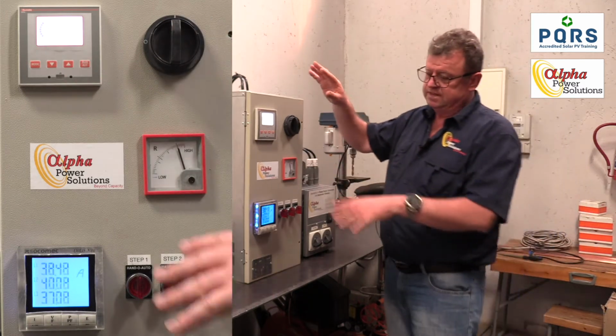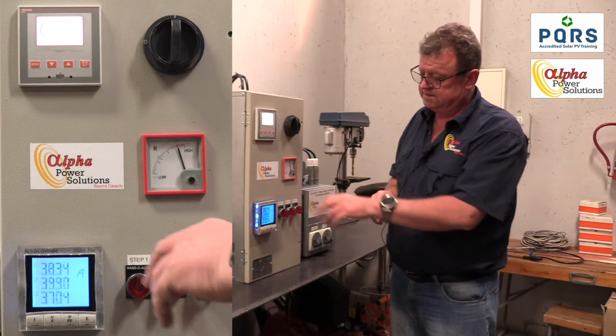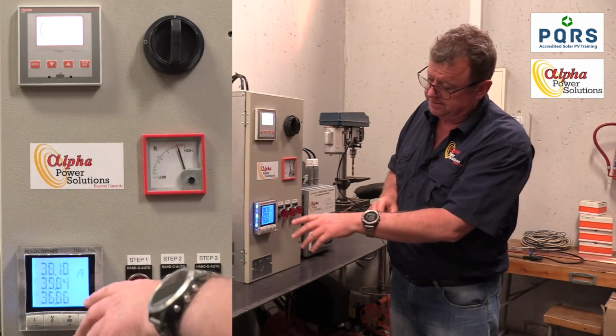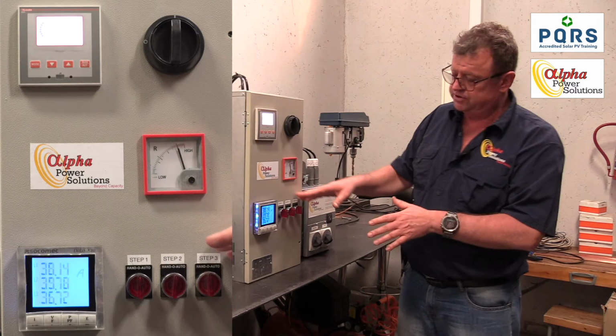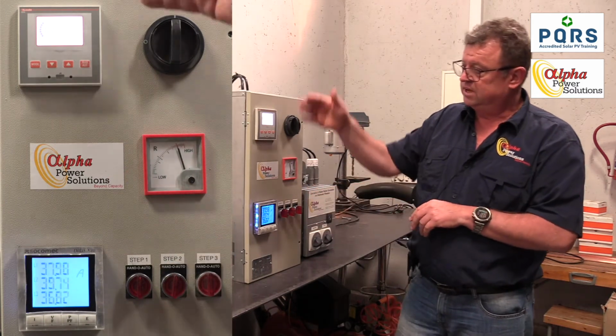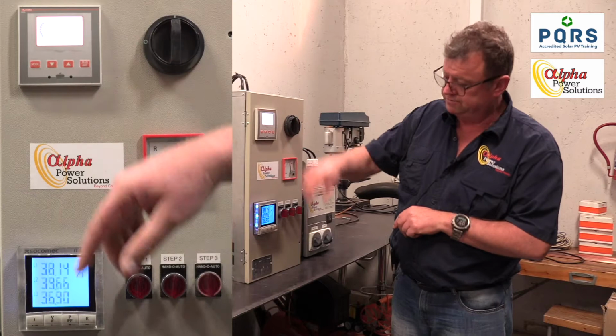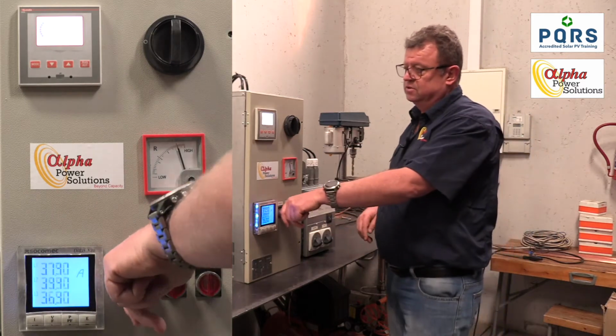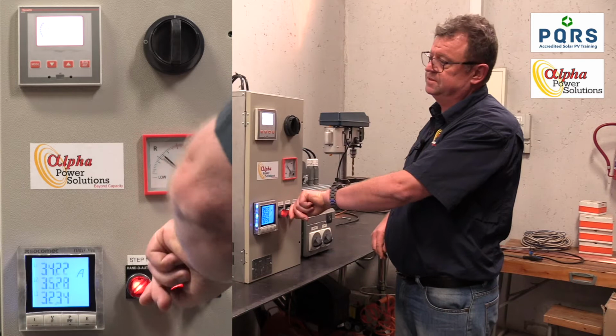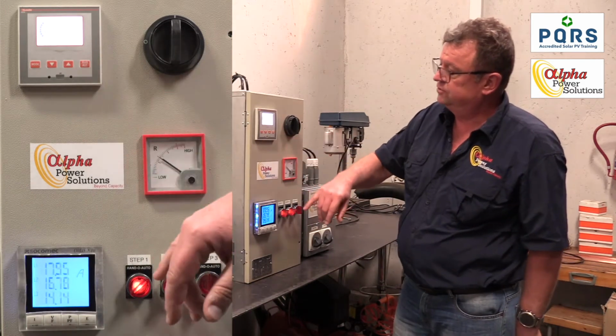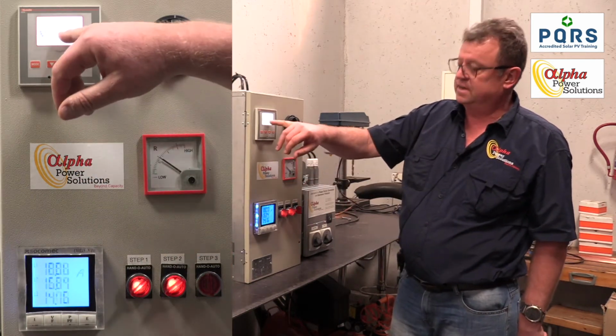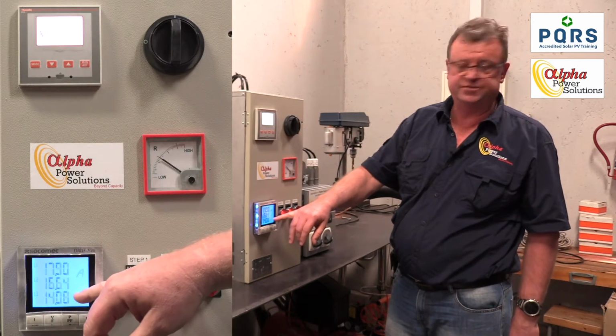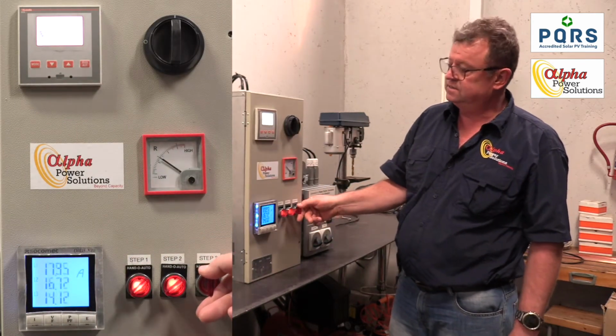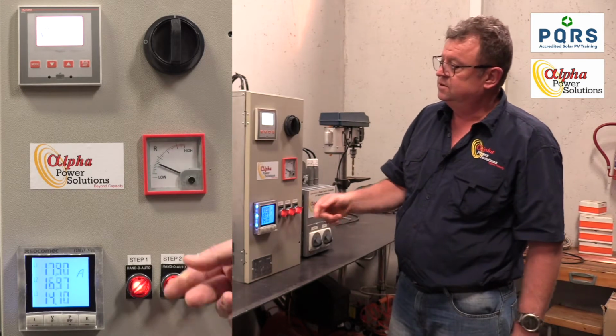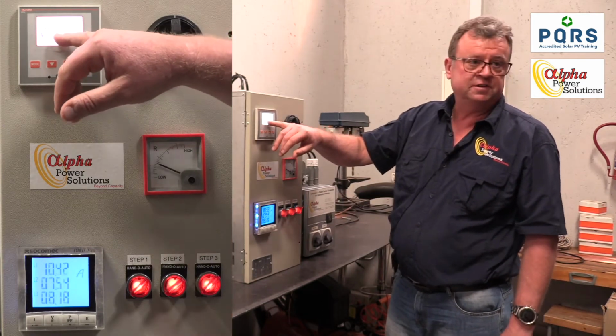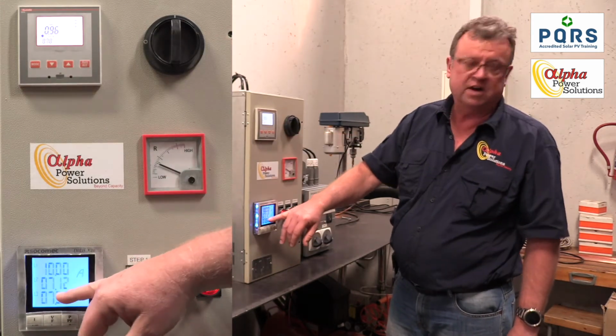So inside here we have a bunch of capacitors, and we will bring the steps in. There's 3 steps in this little demo unit, and I would like you to watch what happens to the power factor and the current. I'll start with the first 2 steps, and you see by putting 2 of the steps in, the power factor has improved and the current has dropped quite dramatically. And if I bring in the 3rd step, the power factor improves to almost perfect at 0.96, and there's hardly any current left.